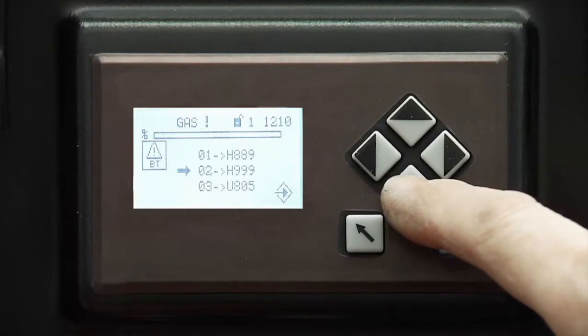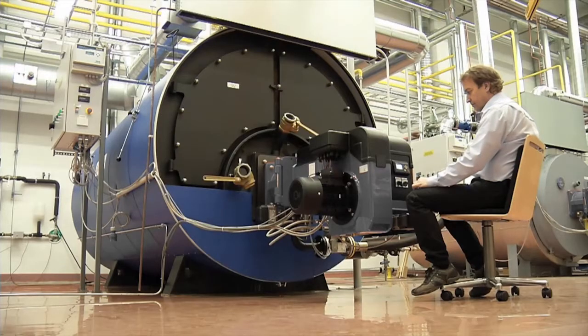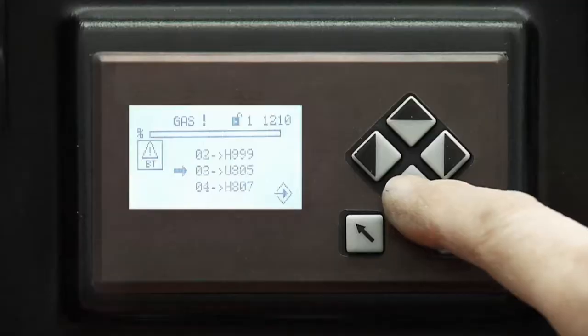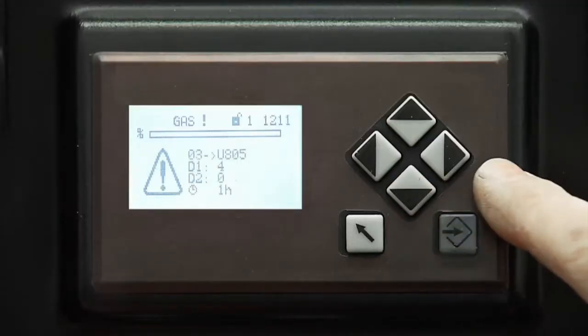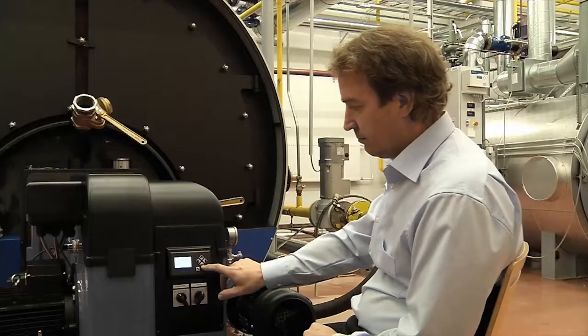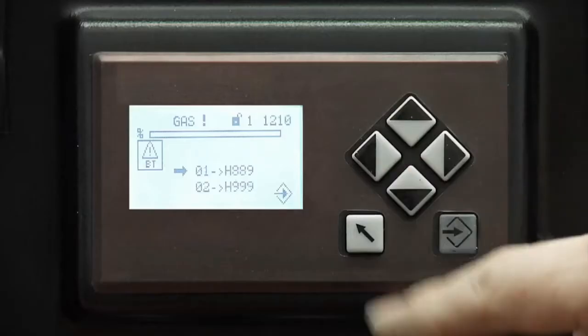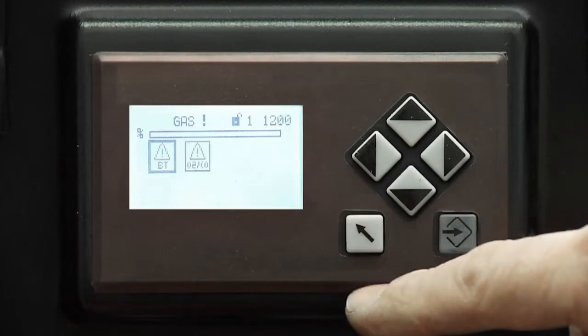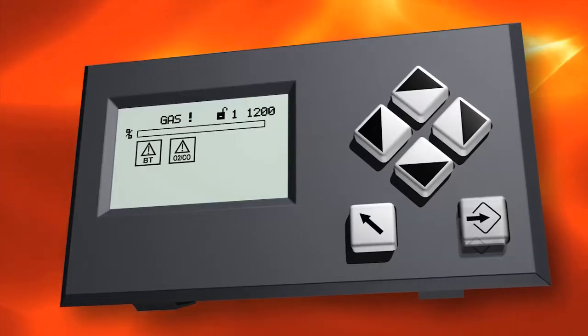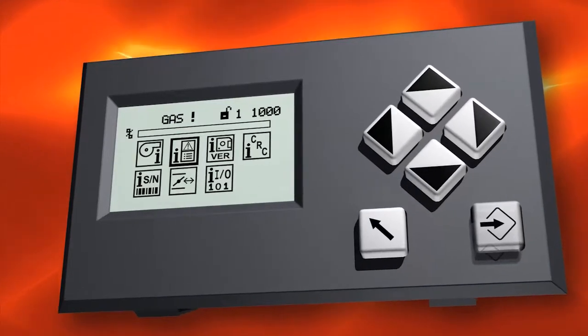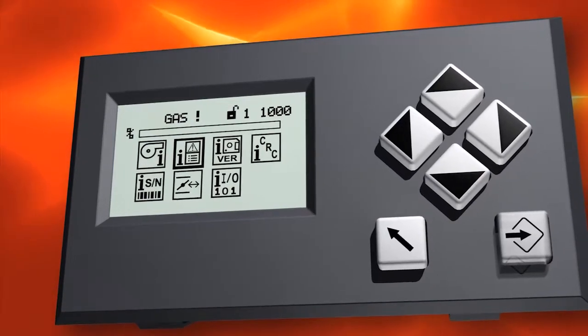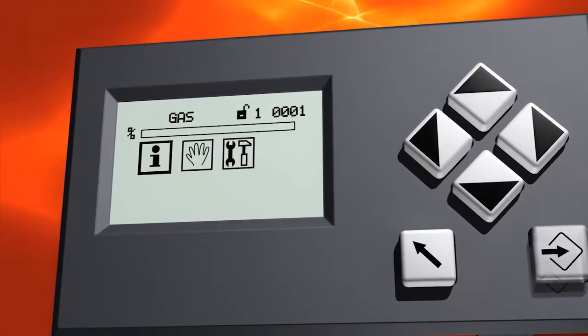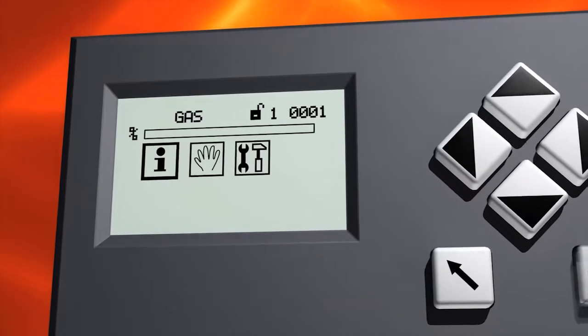You can browse through them, and if you require more information on a specific fault, just press Enter to see the details. Detailed information on the error codes can be found in the documentation. Pressing back repeatedly will take you back to the main menu. Now that you've carefully commissioned the burner, LAMTEC BT300 system will operate your burner efficiently.